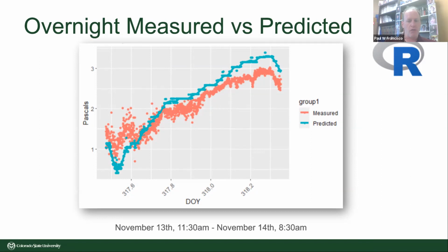So a quarter of a Pascal might be almost nothing in terms of pressure, like a single ply piece of tissue on your hand, but it could also be like 10% of the entire driving force you have to have air coming into the house. One of the challenges of this project is we're dealing with very small pressure differences that could still be important.